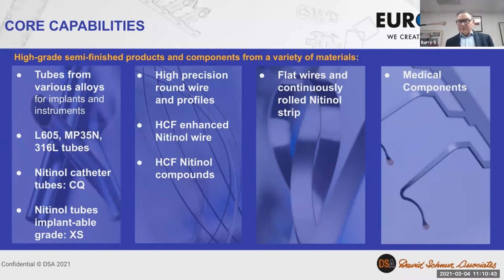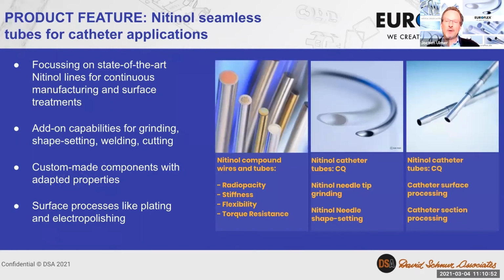Great. So generally, what applications are best suited then for catheter quality tubing? I would say anything which is what we call the over the wire catheters. You have an inner tube where you push the guide wire through, and an outer tube where you put the pressure through, for example, for blowing up the balloon. To make that stiff enough and flexible enough to go around the curves, nitinol is a very good material, because one of its capabilities is what the industry calls superelasticity.